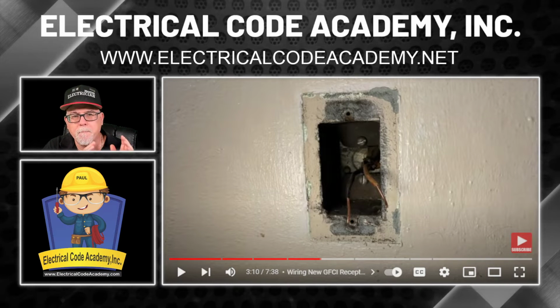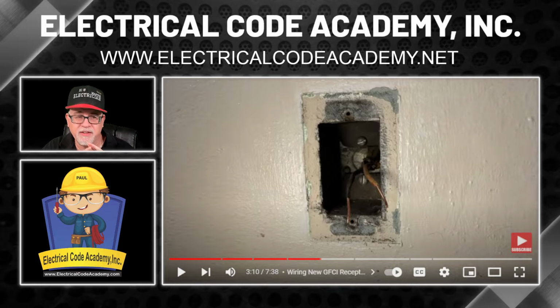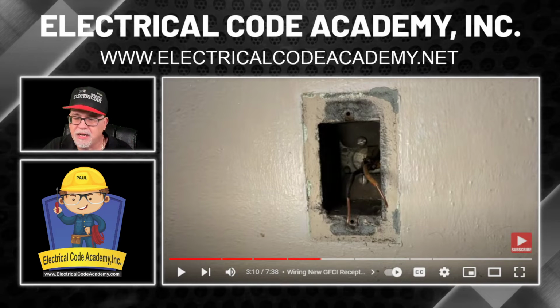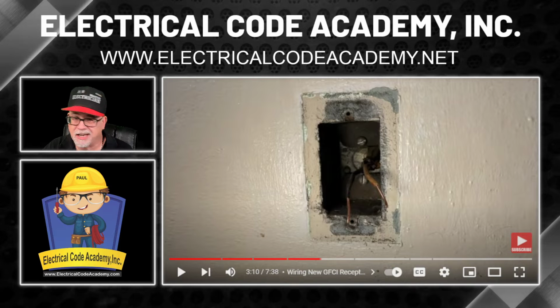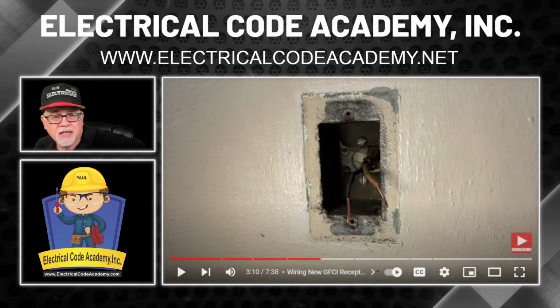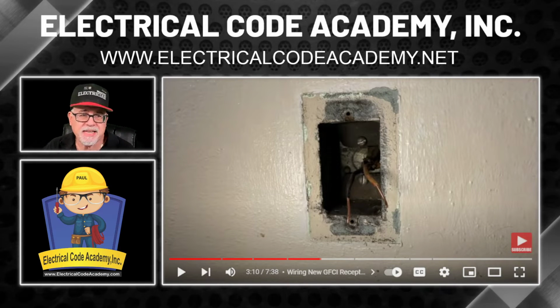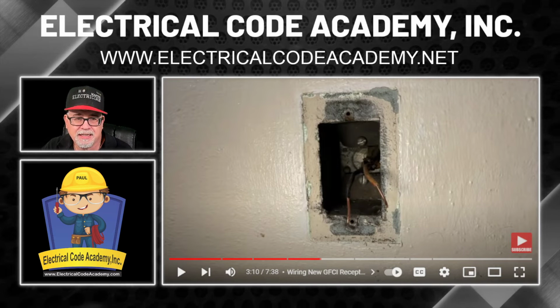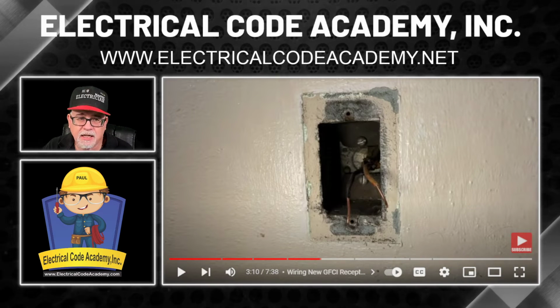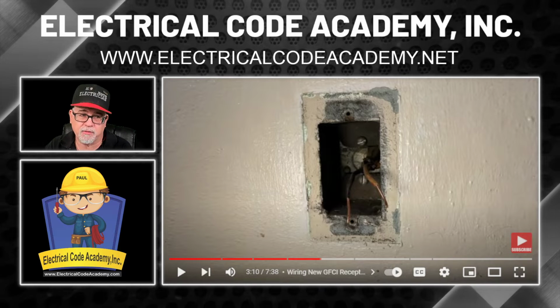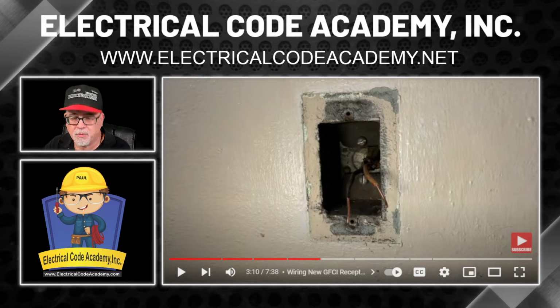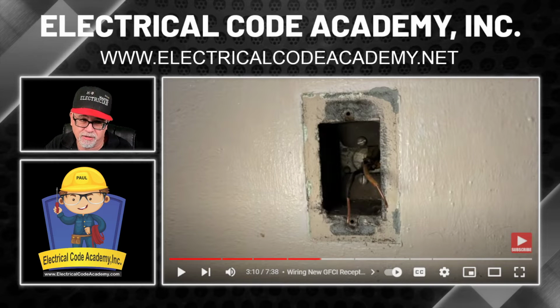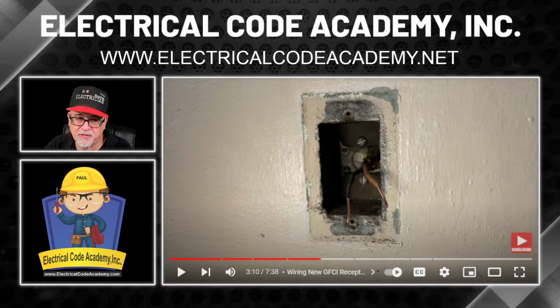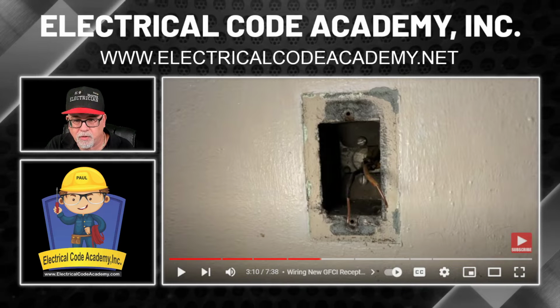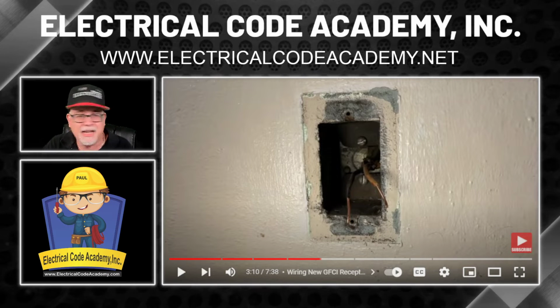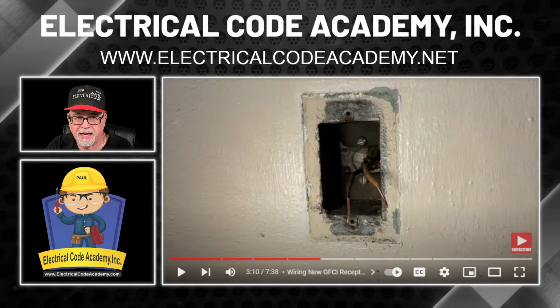Totally different than the old BX style. That was not for use in any of that armor as anything to do with an equipment ground. So again, older homes like this probably have an old BX style armor. Just remember, just because it's armor doesn't make it an equipment ground, okay? There is a difference between AC cable and MC cable, and BX is neither. Although it's very common for people to say BX, BX, BX when they're talking about AC or even MC, it is not the same. Okay. Want to throw that out there.